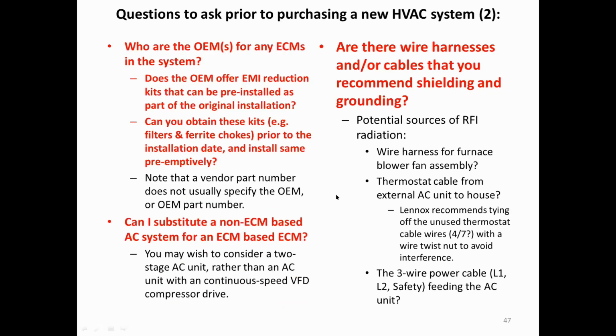If they say, well, we're going to have to use a high efficiency motor in the furnace, we're required to by regulation, try to find out who the manufacturer is. Ask if there is a kit available for reducing RFI, and ask or insist that it be installed preemptively if there is. You could ask in each case if you want to substitute a non-ECM, that should actually be a non-VFD, AC system for an ECM-based system. And here you may wish to consider a 2-stage AC unit, which I'll talk about in a minute, rather than an AC unit with a continuous speed VFD. I have the latter, and I'm going to talk about an alternative.